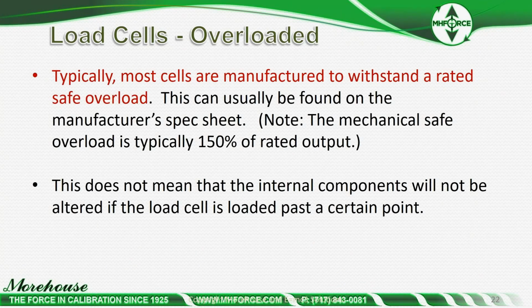Typically most cells are manufactured to withstand a rated safe overload. This can be usually found on the manufacturer's spec sheet. The mechanical safe overload is typically 150% of rated output. Our cells are shear web load cells. If you have a 5,000 pound shear web load cell, you will not shift the zero balance until you get to around 7,500 pounds. Once you get to that 7,500, you will start to shift the zero balance.